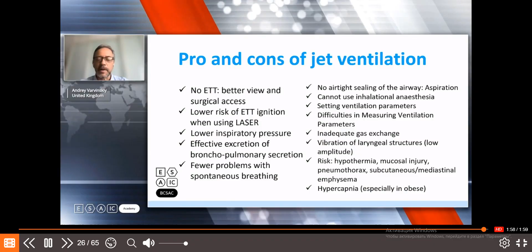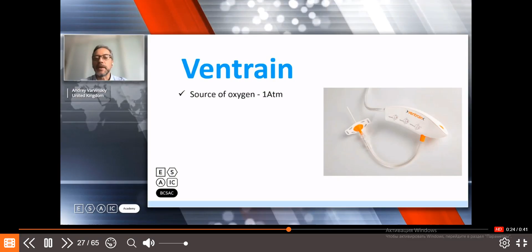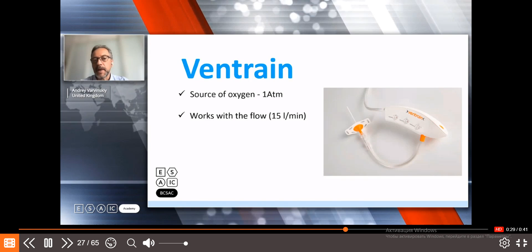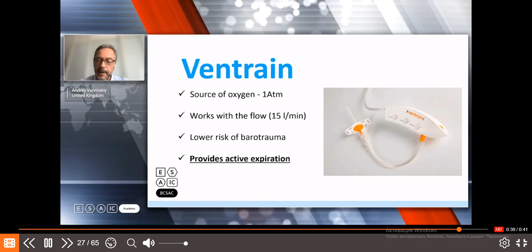I've mentioned to you this device called Ventrain, which is a manually controlled flow control device for providing jet ventilation. The source of oxygen here is at 1 atmosphere, so you're connected to a normal source of oxygen, which you will find anywhere. You don't need Sanders injectors or a manual jet, and you don't need to connect it to a higher pressure source of oxygen. It works with a flow of 15 liters per minute, which is the maximum one can use. There's a much lower risk of barotrauma because you're only using 1 atmosphere. And most importantly, it provides active expiration.